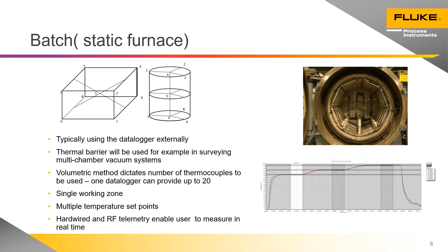And this slide just shows something that most of you will be familiar with. This is a typical survey frame. So we can see that the working volume here is rectangular, despite this being a cylindrical furnace. It's quite normal. And we can see the thermocouples tied to the frame. The exit is down at the bottom right-hand corner of the image there. This is going to be a survey that's done in real time. So the data logger is mounted outside of the process, measuring the temperature from those thermocouples that are typically tied to that frame with nickel wire.